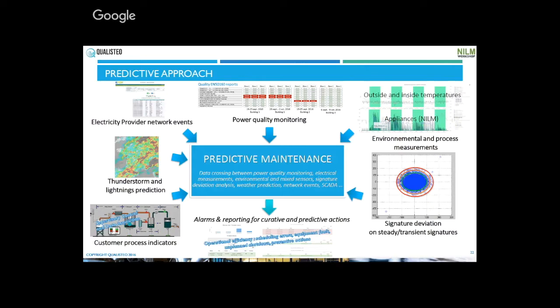So our proposition is: by crossing the NILM algorithm with current and voltage measurement, like electricity provider network events, by providing power quality monitoring with good accuracy according to several standards, by crossing environmental and process measurements, by introducing new sensors like acoustic, vibration, and temperature sensors, by including prediction and forecast, and by coupling the SCADA interface — supervisory control and data acquisition from your customers, for example — and by studying the NILM algorithm signatures and signature deviation, we can make quality reports and generate alarms for curative and predictive purposes.